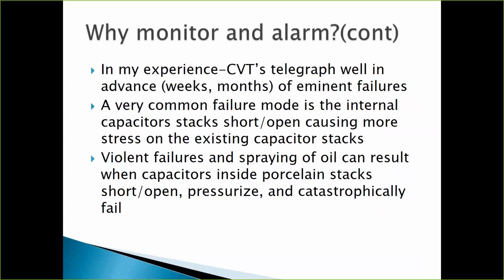We can exploit the fact that a common failure mode is the capacitors short or go open. They do it one at a time, then another one before they have a catastrophic failure. And this happens, again, weeks and even months prior to that failure event. I mentioned to you before the violent failures, they spray oil.